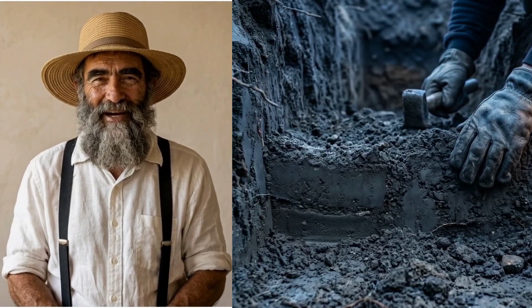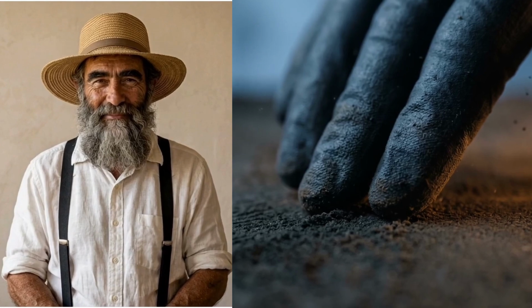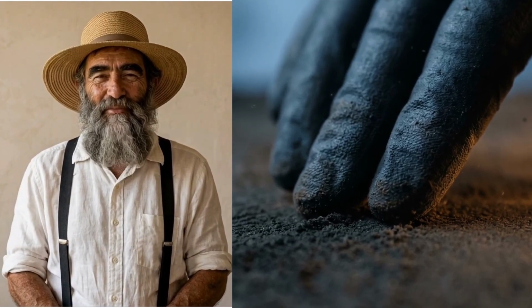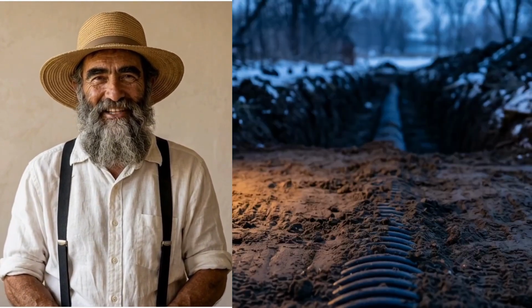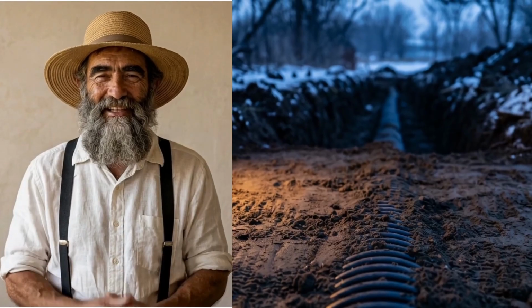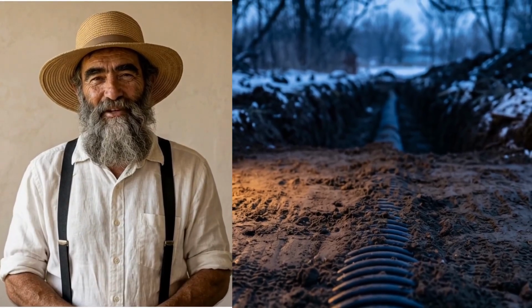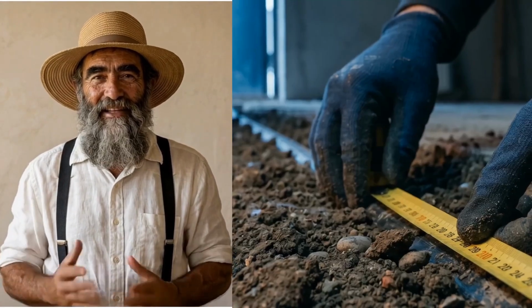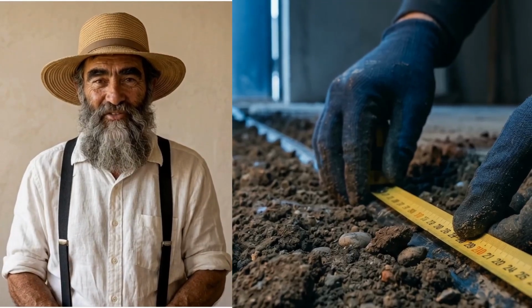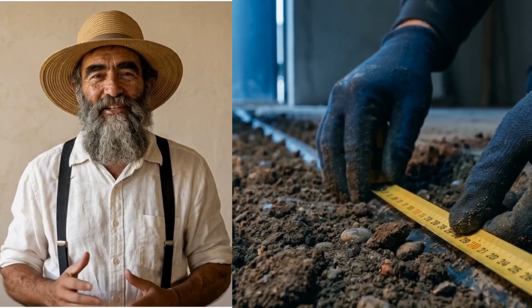The goal is maximum surface contact between the pipe exterior and the soil. Do not use PVC. PVC cracks underground over time. HDPE flexes. Step 4. Backfill the trench with the native soil. Tamp it down in 6-inch layers to ensure contact. No air gaps. Let it settle for 1 week.